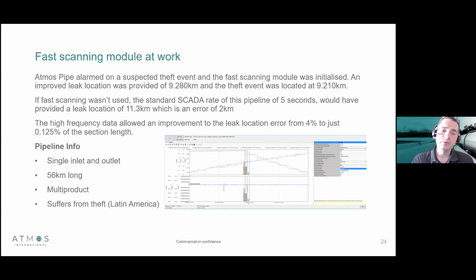If we weren't using our fast scanning module and we were just using the standard SCADA rate on this pipeline, we would have had an error of 2 kilometers. So by being able to collect this high frequency data, we've improved the leak location of this system from 4% to just 0.125% of the section length. That's a huge, significant improvement.